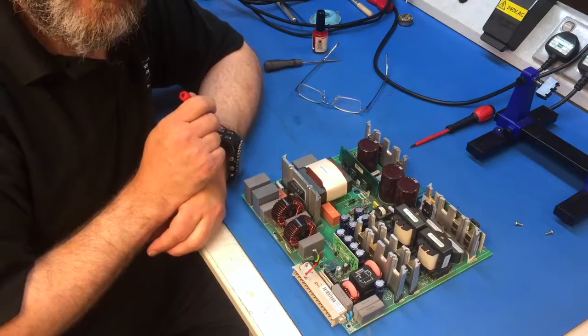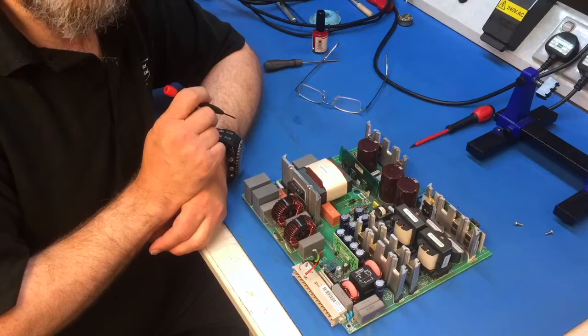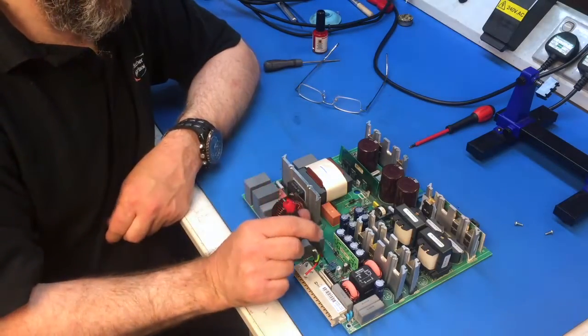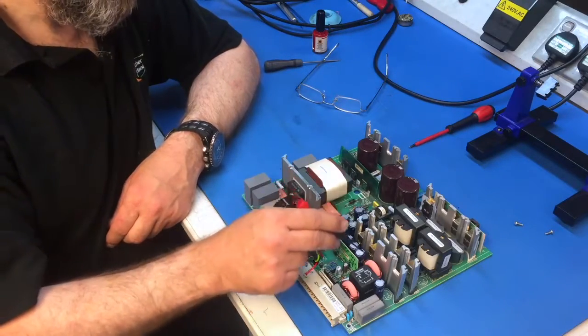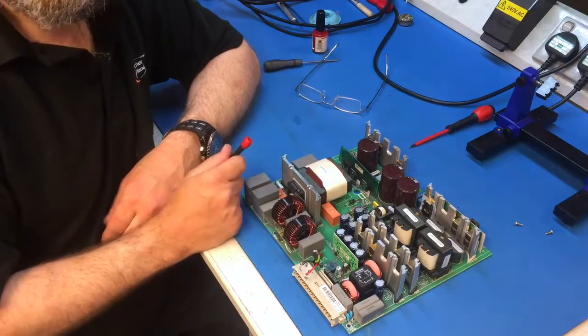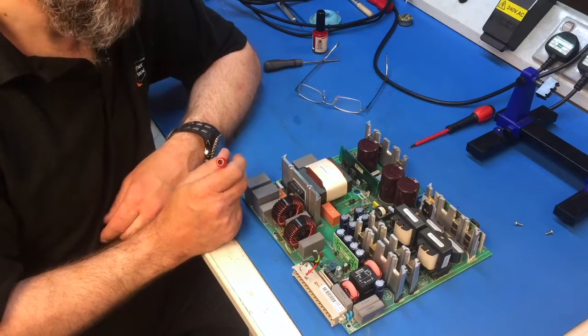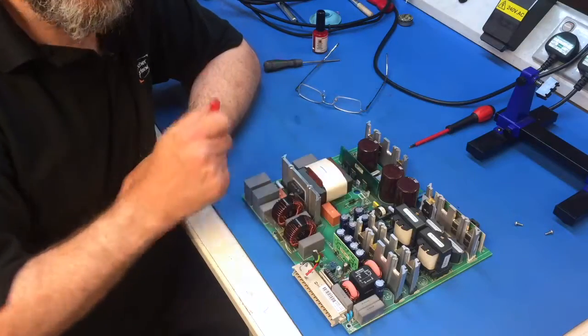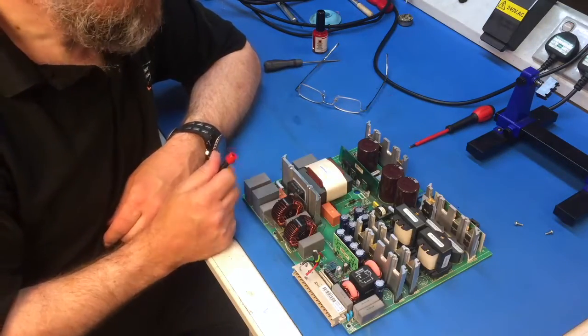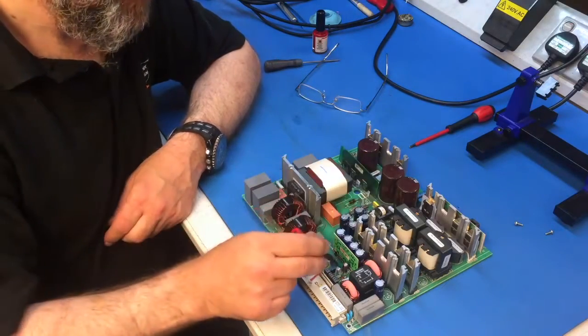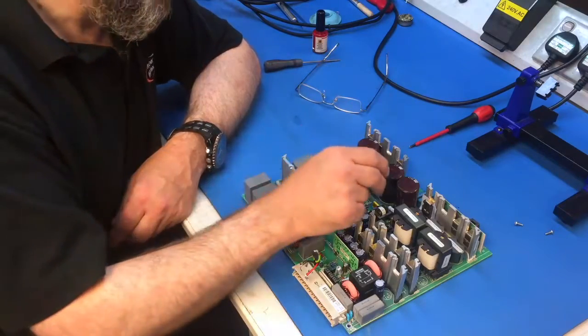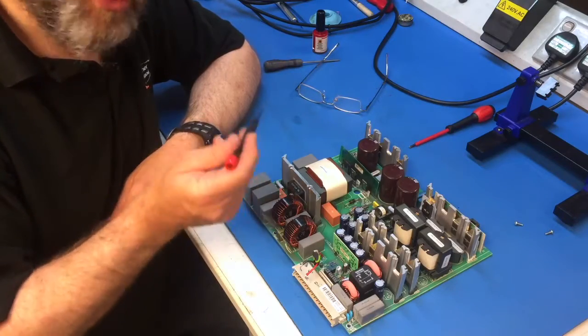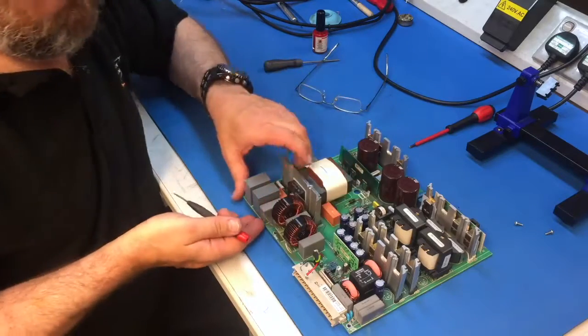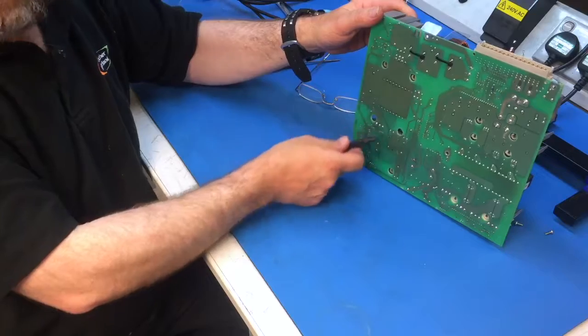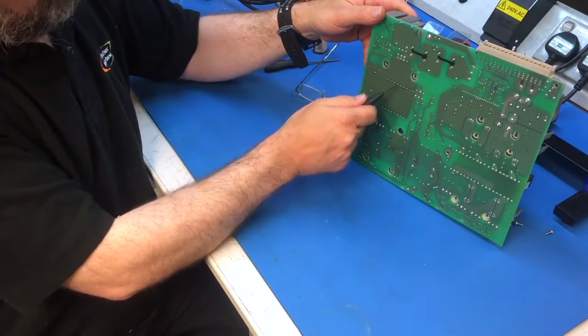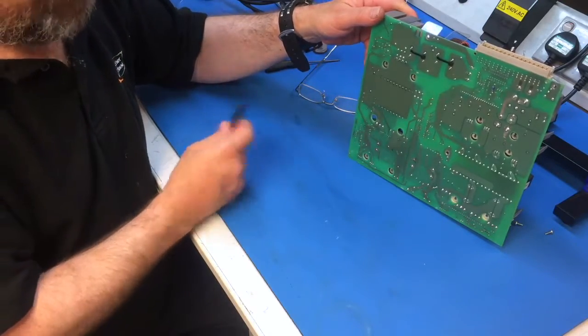We also identify what we're going to change in our standard overhaul - anything that can affect the reliability of the power supply after we've carried out the repair. Things like relays and electrolytic capacitors, which age with time and temperature; high temperature and high ripple currents shorten their lifetime considerably, to about 3 or 4 years sometimes. Opto-isolators degenerate with time and lose their sensitivity, so we have to replace those. We look at the power resistors for any obvious signs of burning, which means they may be likely to fail soon, and capacitors for cracking in the cases, which could allow moisture in and cause them to fail. Then we check the solder joints on the board, particularly on large heavy components like transformers, looking for cracking of the joint - a little circular crack around the wire - which causes an open circuit and future failure.